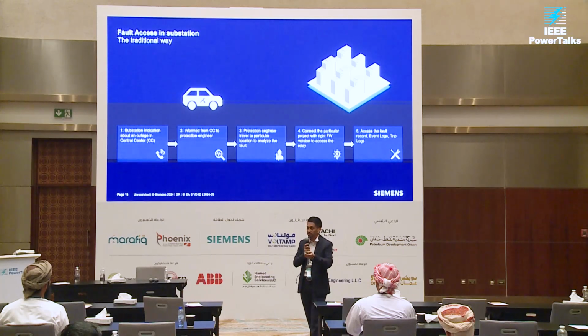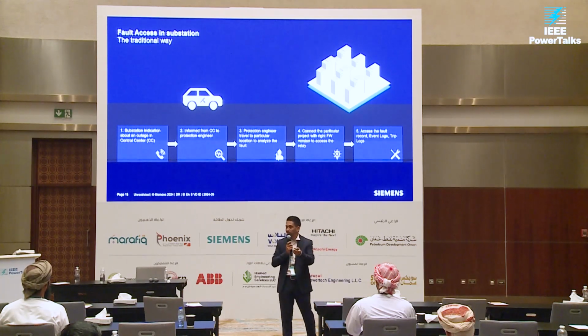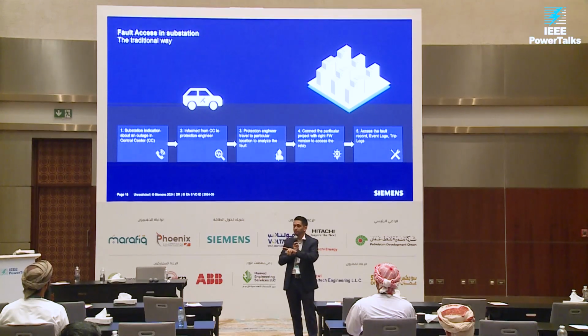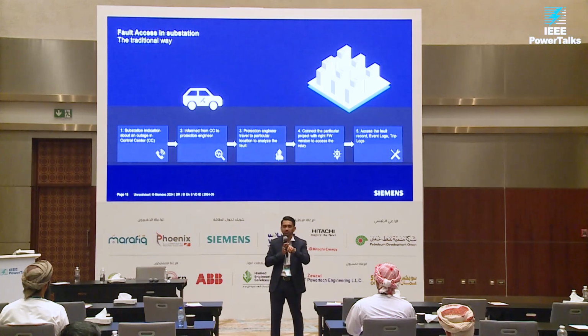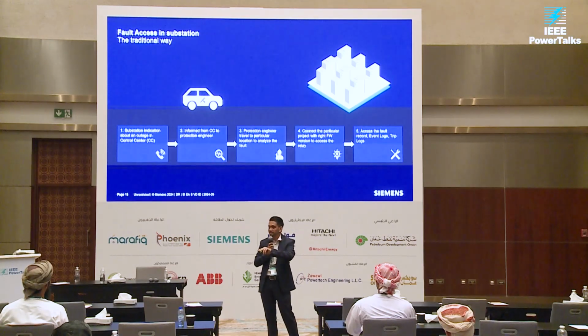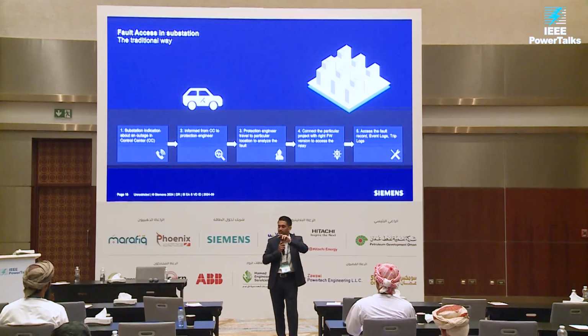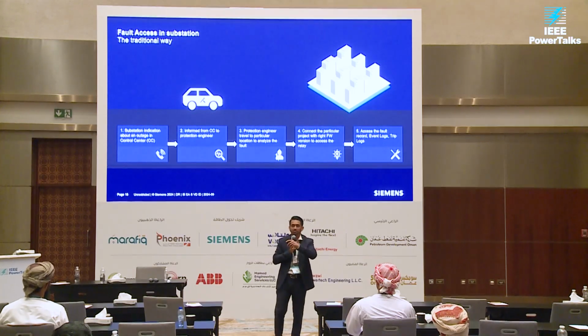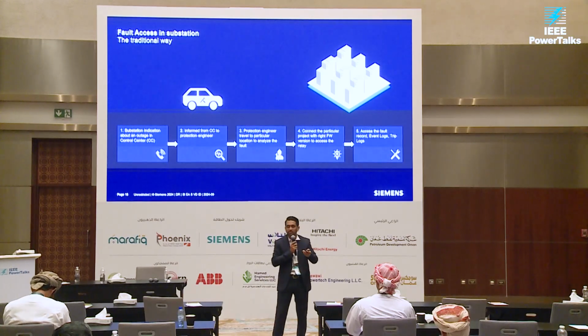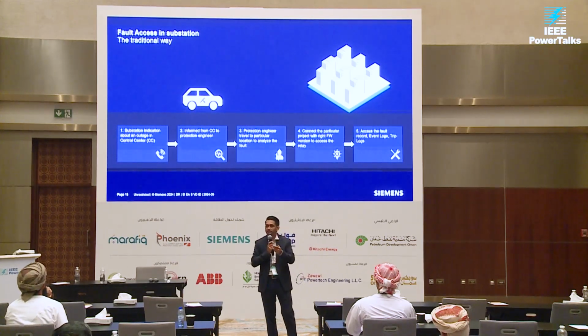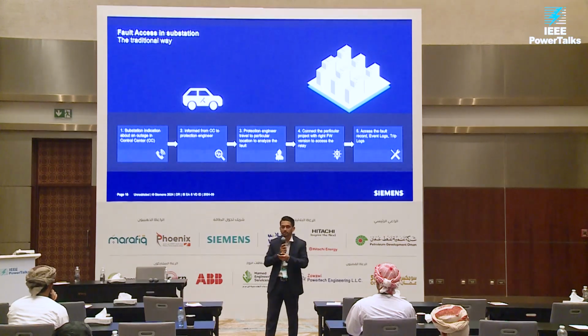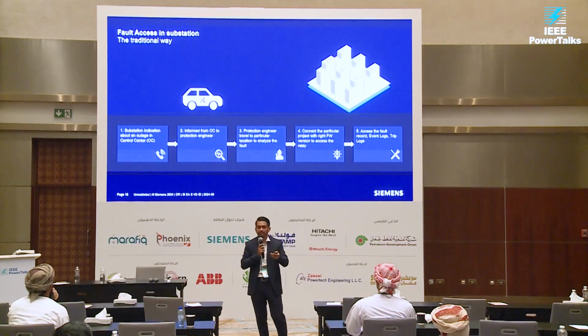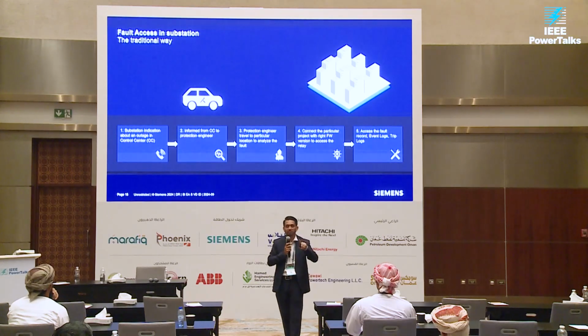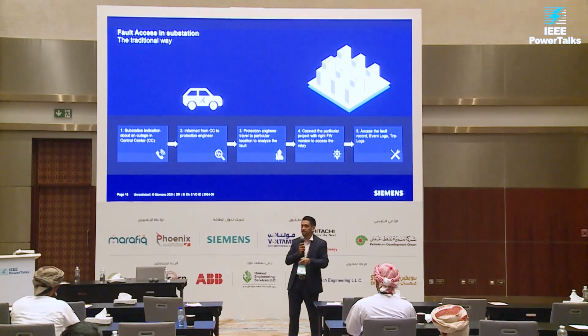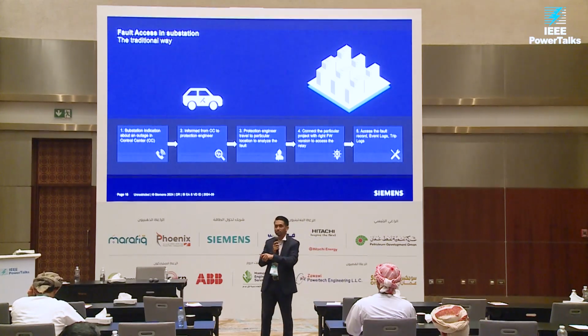He even gets, for example, an email notification when the trip happened, and then he logs into the application. If he has a tab or a laptop, he will see all the information, for example, where the fault happened. Let's say the fault happened in multiple locations at the same time. They will see that it's correlated. If I take a transmission station, it can be that line differential has operated. That means two substations have operated at the same time. So he can immediately correlate. Then he can see the fault records on the app. He does not have to download any third-party software, for example SIGRA, to visualize the fault records. In the same application, he can visualize the fault records and then he can suggest the corrective actions without even having to visit the site.